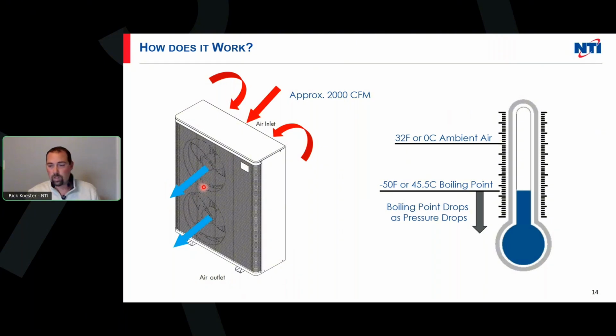We have about a 3-ton, which is a single fan. You'll see that in a minute. But each one of those fans brings about 2,000 CFM of air through that coil. So if I'm moving that much air across, on a 32-degree Fahrenheit, 0 degrees Celsius day, and that refrigerant is at -50, that's a huge temperature difference. So we're absorbing a lot of energy through the air into that coil, which we then boost up, like I said before. We send that into the water and we're putting it into the home.